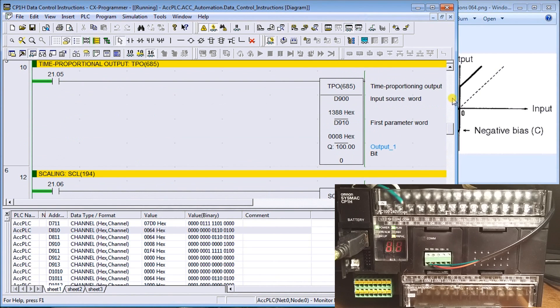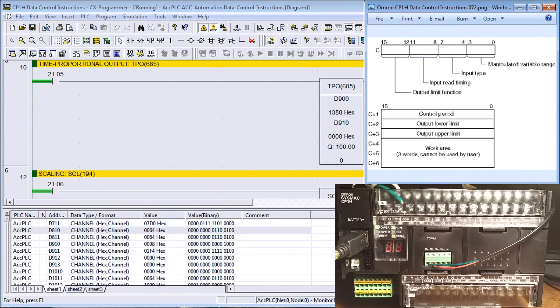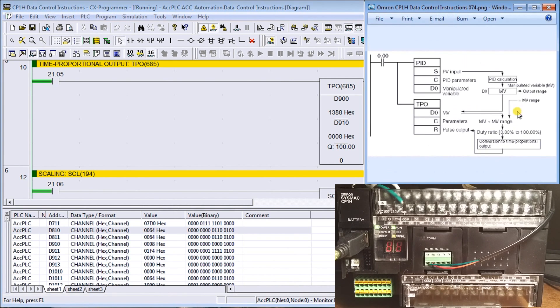The next instruction is time proportional output. It's typically used with PID — it takes the manipulated value and converts it by putting a time frame to it, controlling an output bit. In our case we're going to oscillate an output on our PLC. We have a manipulated variable range and input parameters that must be set prior to using this instruction, all documented in the manual or at accautomation.ca.